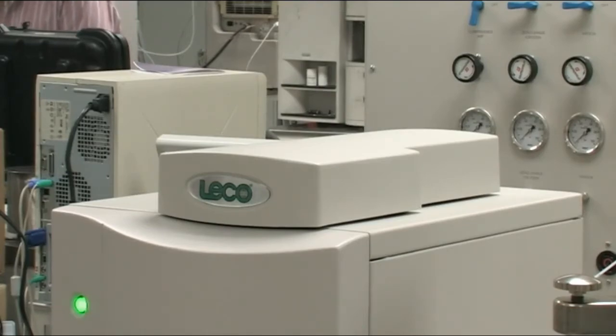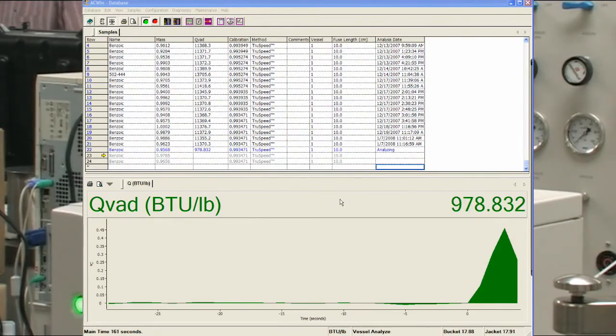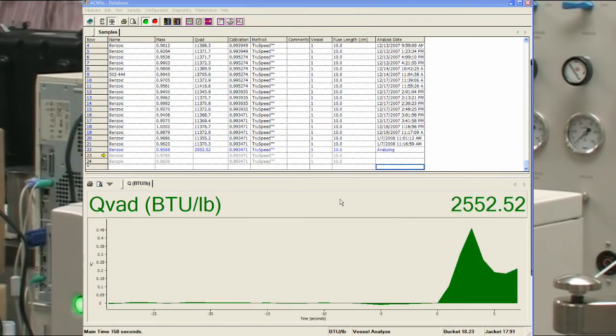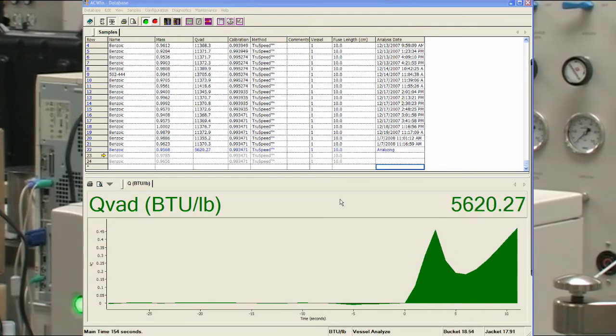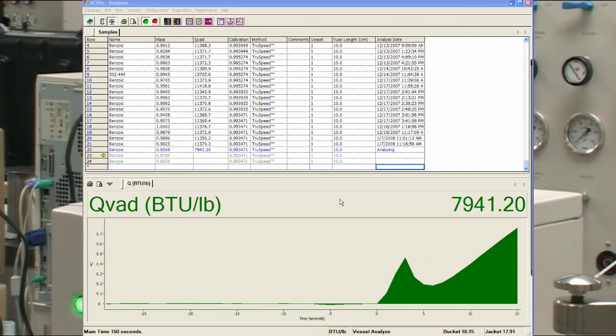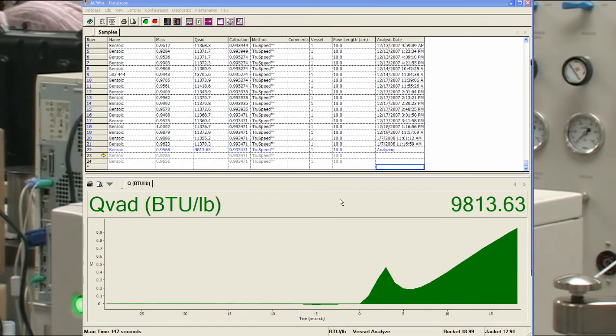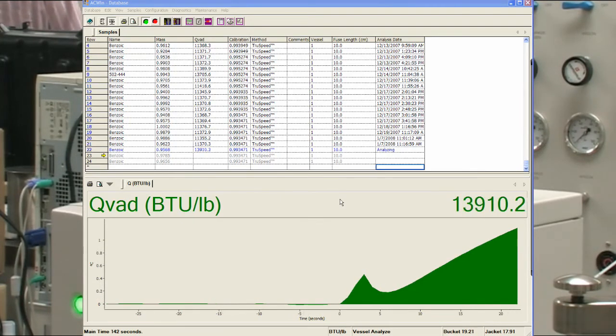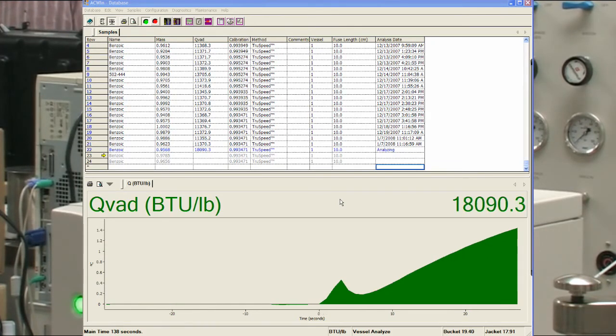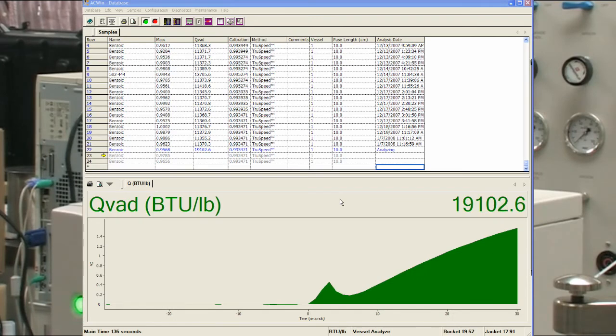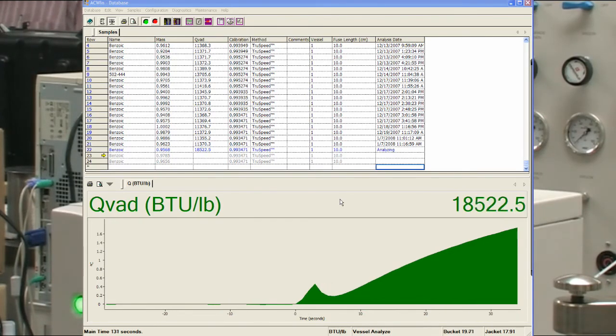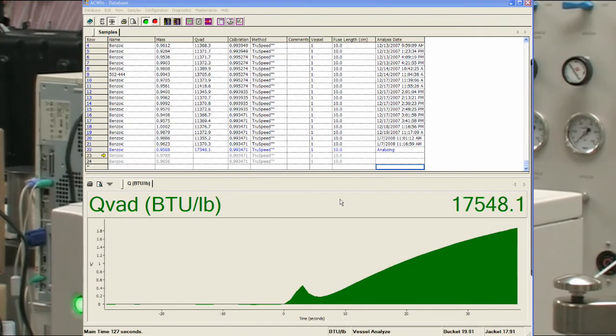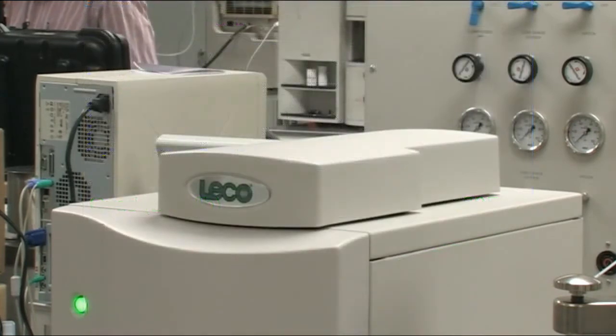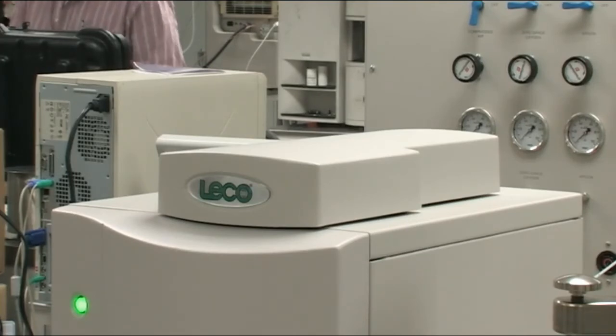The alarm will sound twice when it's about to fire. A couple things to watch for is to make sure about 6 to 7 seconds in the actual analysis time that you see that the vessel has fired. When the analysis is finished, the lift mechanism will bring the bucket back out of the water, and you're ready to place the next combustion vessel in place to run the next analysis.